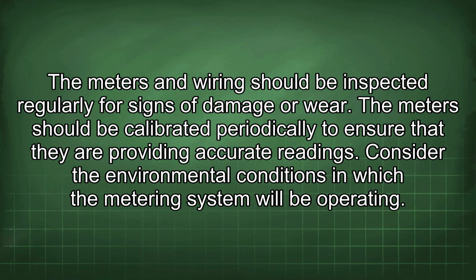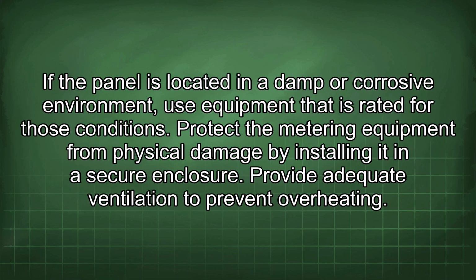Consider the environmental conditions in which the metering system will be operating. If the panel is located in a damp or corrosive environment, use equipment that is rated for those conditions. Protect the metering equipment from physical damage by installing it in a secure enclosure. Provide adequate ventilation to prevent overheating.